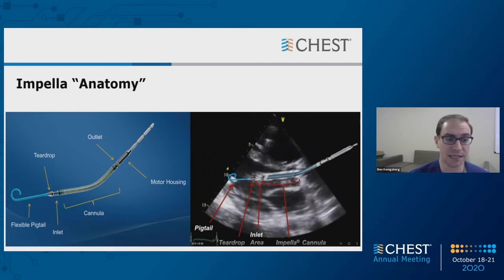Starting at the tip, we have a flexible pigtail catheter, which is visible on ultrasound. More proximal to this is the inlet of the device, and separating and identifying the distinction between the inlet and the pigtail catheter is an echogenic teardrop, which is metallic and easily visualized on ultrasound. The inlet is where blood is sucked into the device.